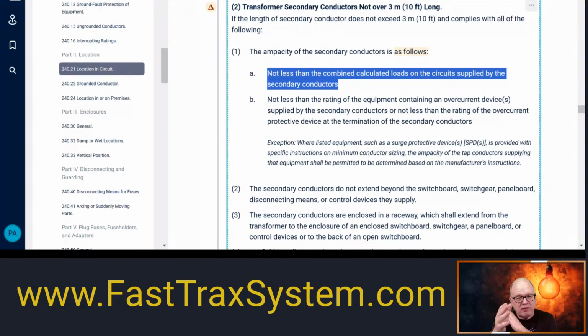You would treat each separate, but you also want to make sure that transformer can handle those multiple loads. I don't know how many of you have actually seen a transformer feeding multiple loads, but you can. There's nothing that says you can't do that. But one thing's for sure: if we're coming out of the transformer and hitting that panel with that breaker, we want to make sure the conductors can at least handle the combined load that's going to be in it. So you're going to have to do a load calc. You're going to have to know what you're putting in that panel.